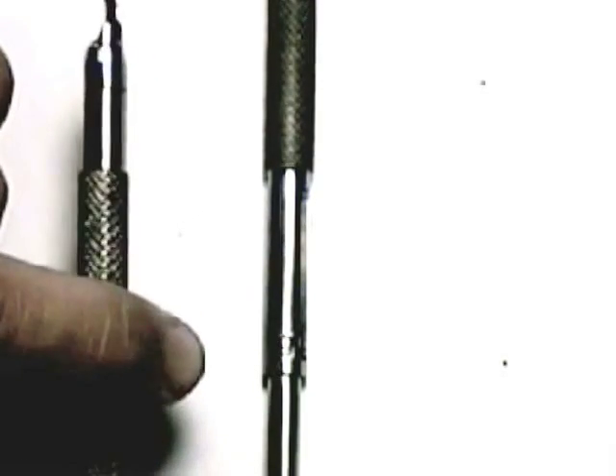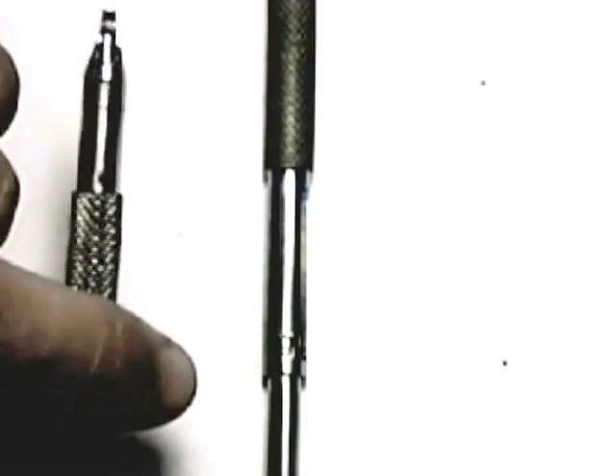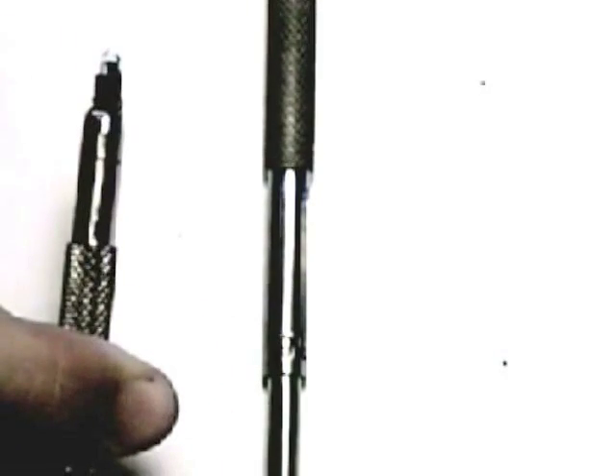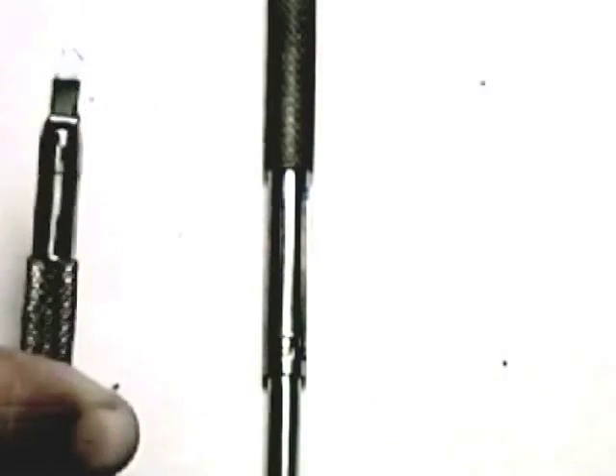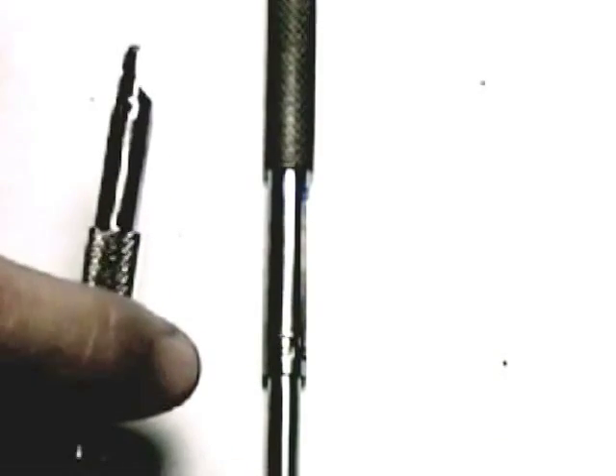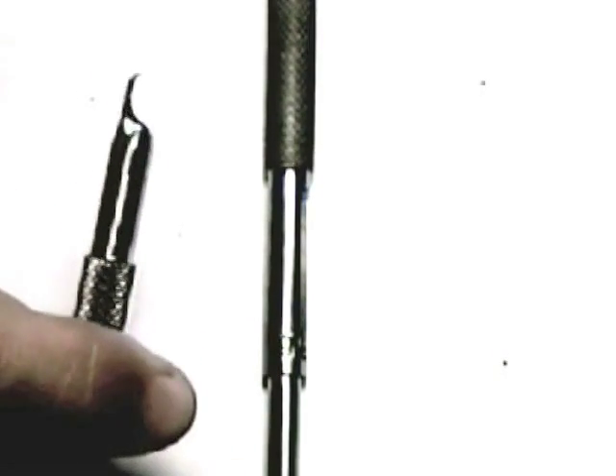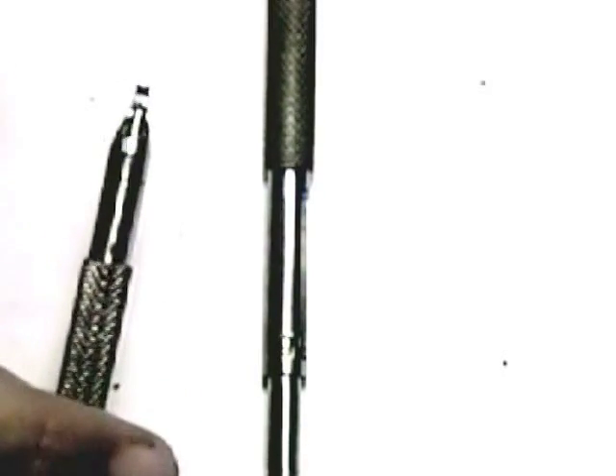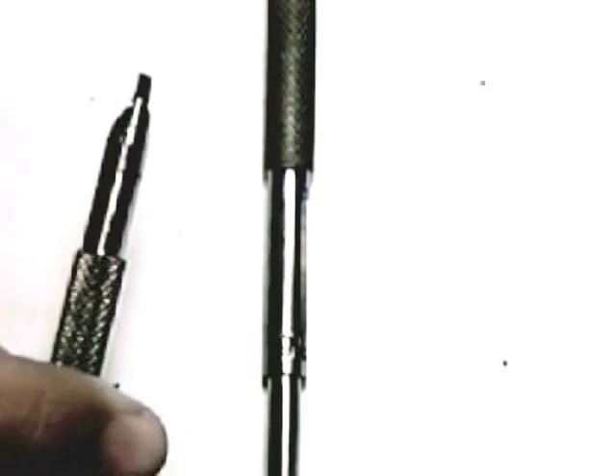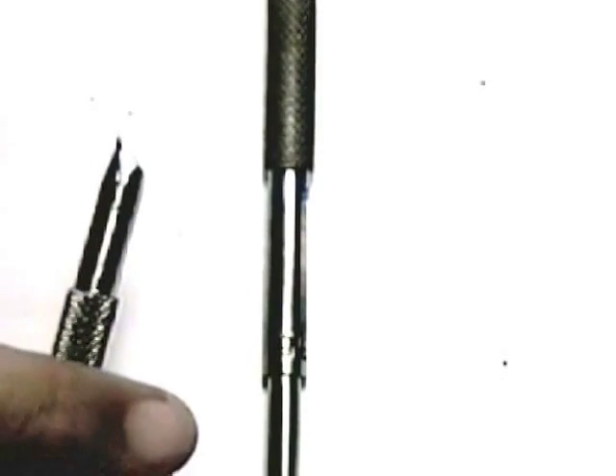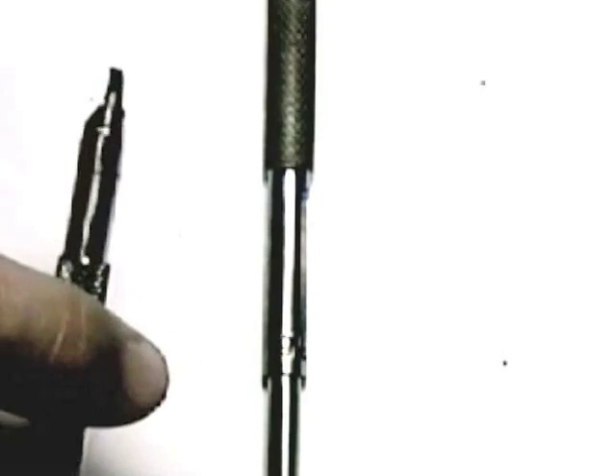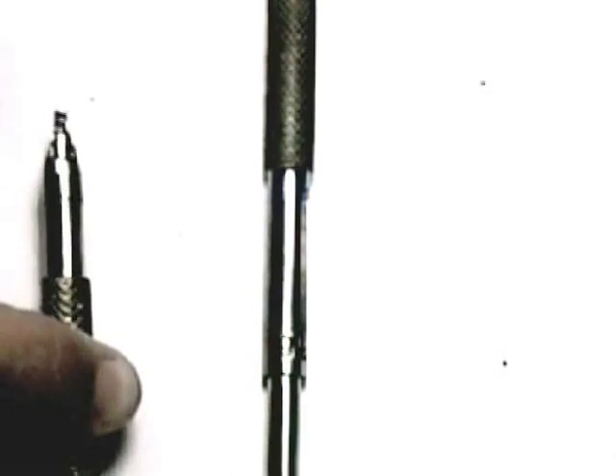These diamond knives can be autoclaved and sterilized in any manner. One of the things I recommend is that if a surgeon is going to be using this knife all day, after the first use I would retract it back into the handle, place it in a pan of water just so that debris is not allowed to form on the blade. One of the things that impacts the performance of these blades is dried tissue, which is allowed to bake onto the blades during the autoclaving process. So I would always keep the blade in a pan of water when it's not in use. And we also do sell diamond knife cleaning blocks, which are used to clean off the debris on the blade should any settle on the blade. So again, right after use, retract it back into the handle, hand it to the assistant, and then the assistant can place it in a pan of water, and that keeps the blade hydrated until it goes into the autoclave.